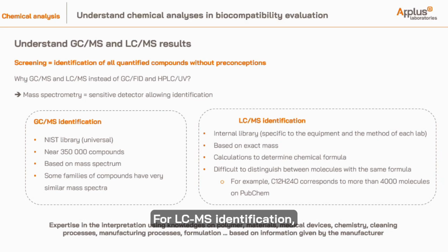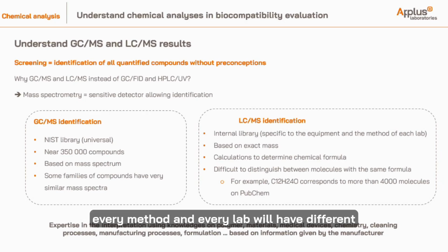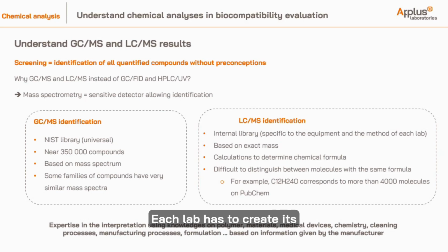For LC-MS identification, the work is more difficult to perform because every equipment, every method, and every lab will have different results, and we can't use a universal library. Each lab has to create its own library based on its method and its work. The interpretation is based on the exact mass measured by the detector, and calculations are performed to determine the chemical formula that can correspond to the exact mass measured.